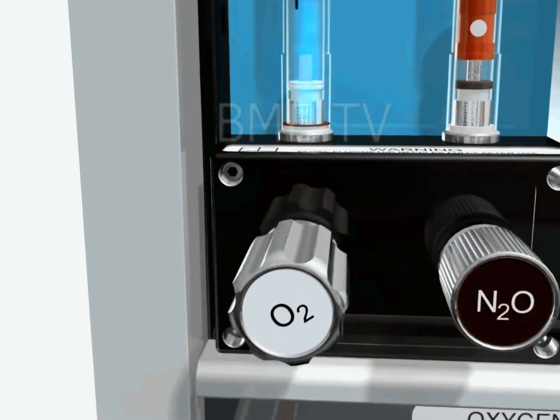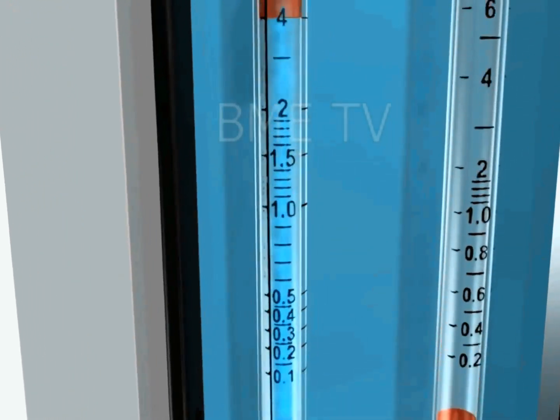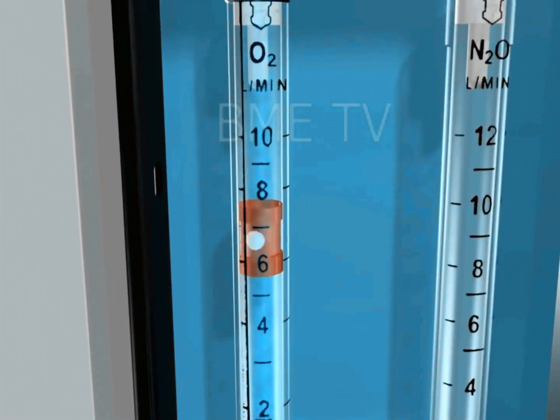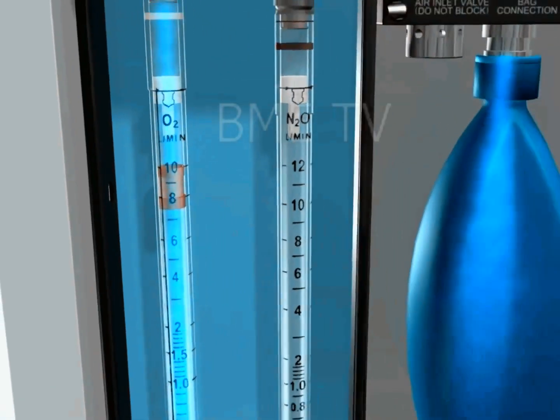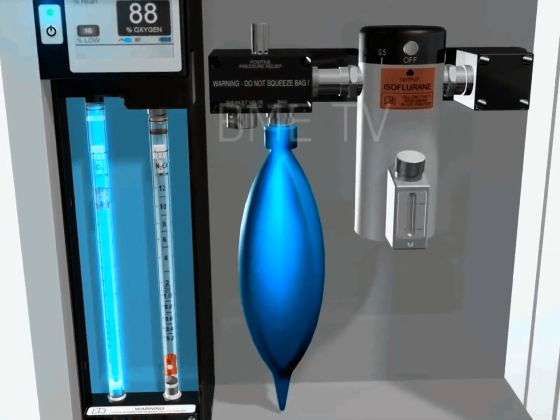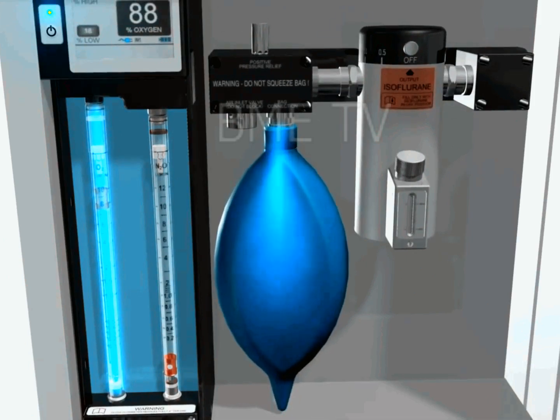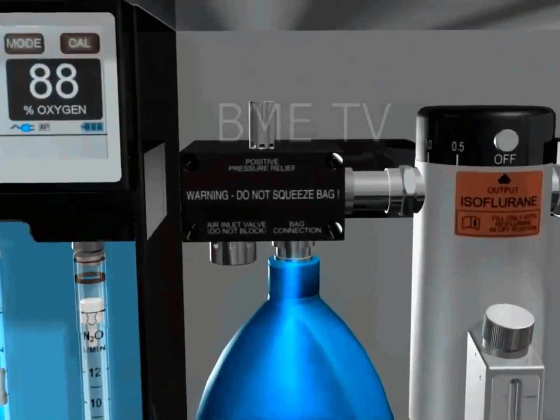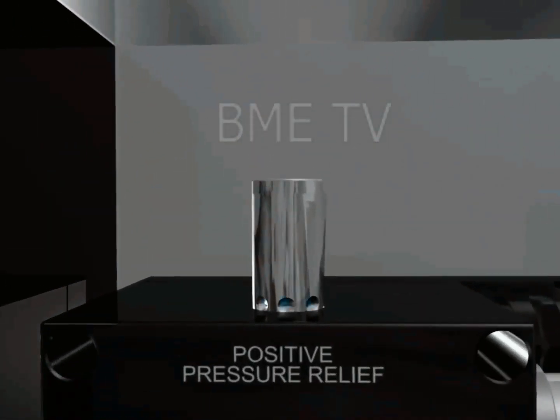Pressure gauges, regulators, and pop-off valves to monitor gas pressure throughout the system and protect the machine components and patient from excessive rises. Flow meters such as rotameters for oxygen, air, and nitrous oxide. Vaporizers to provide accurate dosage control when using volatile anesthetic.